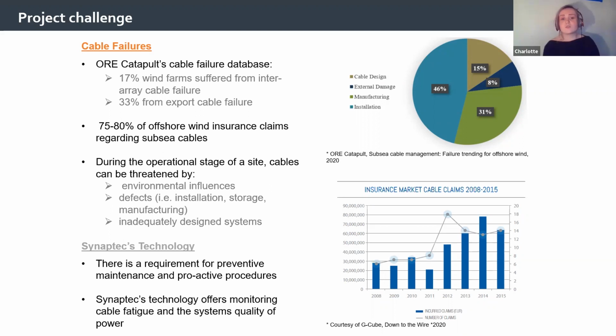Defects can occur from storage, transport, installation, or manufacturing that can also cause damage over time. Or if, for example, the design, production, or installation of the cable has perhaps been executed below the required standards, this can cause problems later on as well. Cable protection systems can fail, leaving the cable damaged or at risk of being damaged, and partial discharge can affect the cable system at various points.